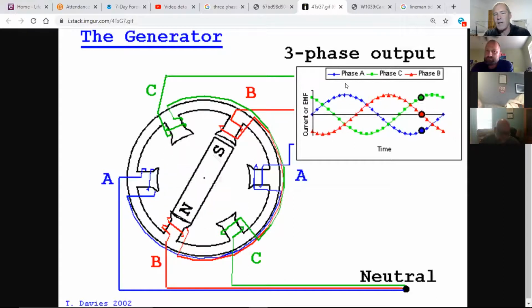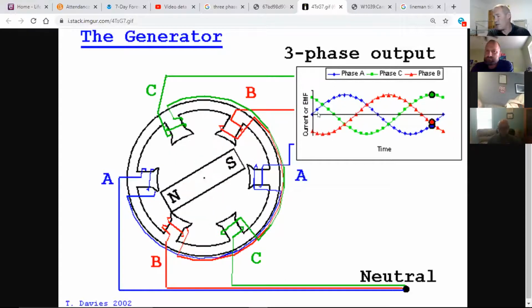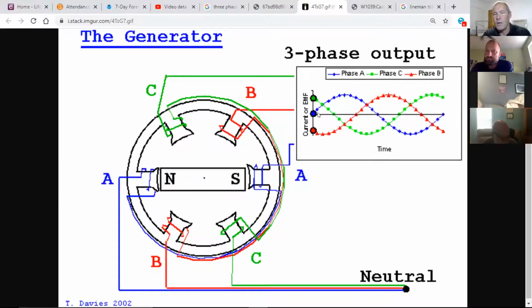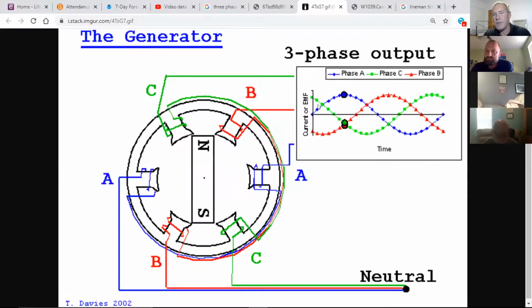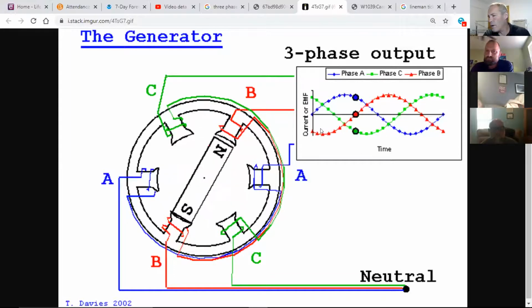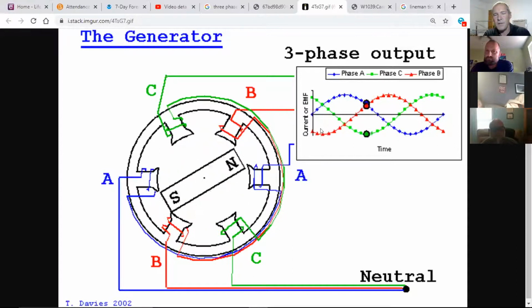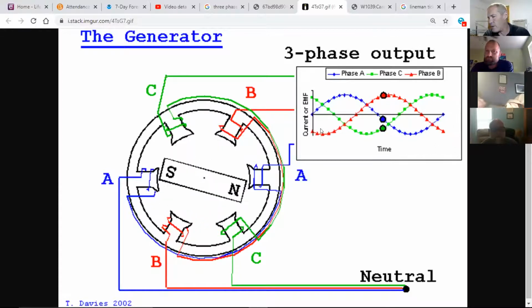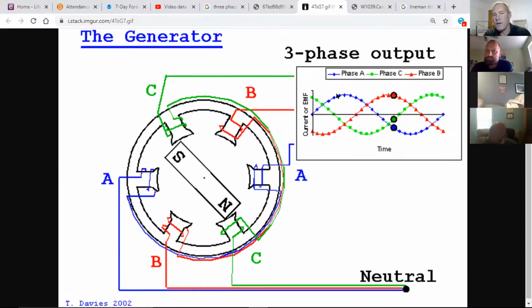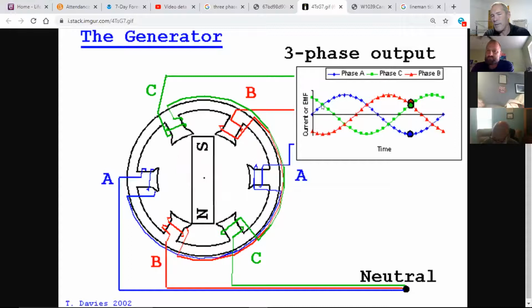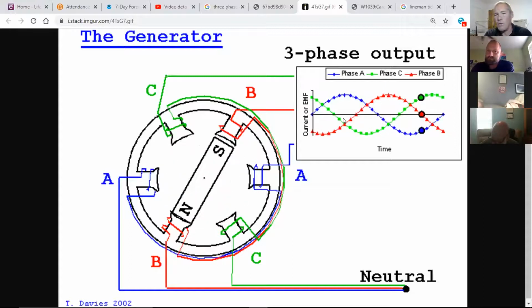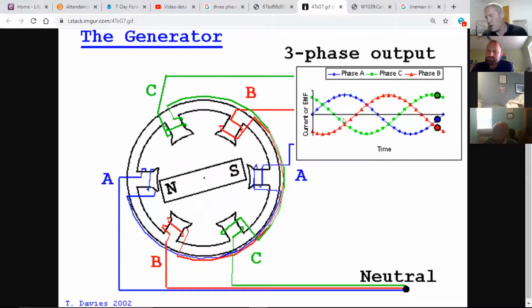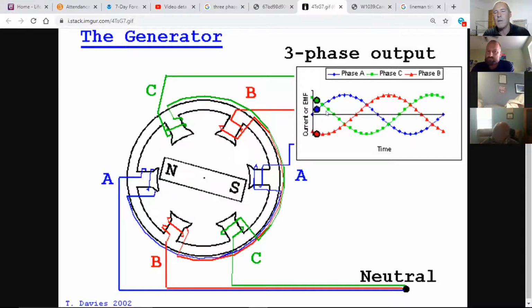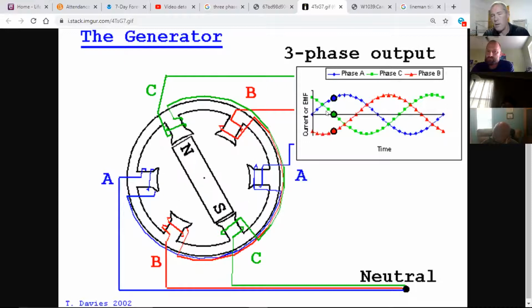This is vitally important when I start working on transmission lines. If I have constant voltage all the time on three phases, I'm actually able to reduce my conductor size even more. One process is stepping up the voltage so I can transmit it. The other is using three-phase, so my conductor can be even smaller and more efficient. It's called load sharing, or like the book says, load balancing. Any questions there? So you can reduce the size of the conductor because it's constant.